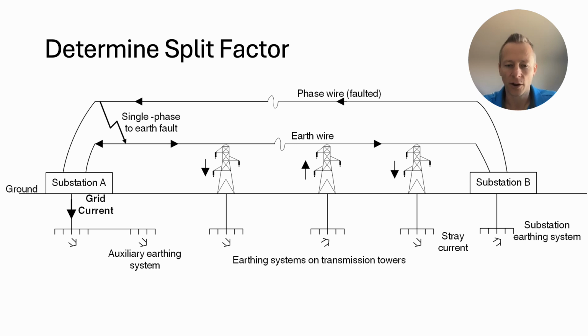So some of that fault current will go into the grid, but it won't actually go from the grid into earth. It'll go from the grid into the neutral conductors and down the distribution lines, and some of that current will disperse back into earth on those distribution grounds, and some of it will go back on the transmission static that's also grounded. So you can see here in substation A in the picture, some of the current is grid current, and some of it is returning on the earth wire. All of it comes on the phase wire that's faulted, and on the earth wire, some of it might go all the way down the wire back to the source, but some of it also splits and goes back on the tower grounds along the way.